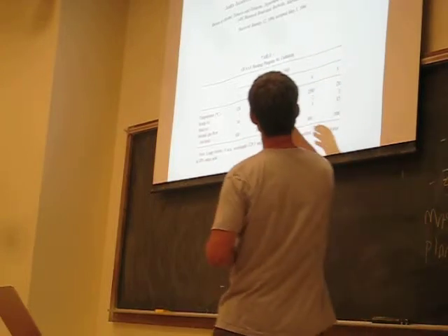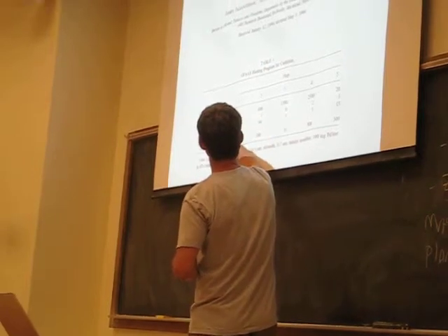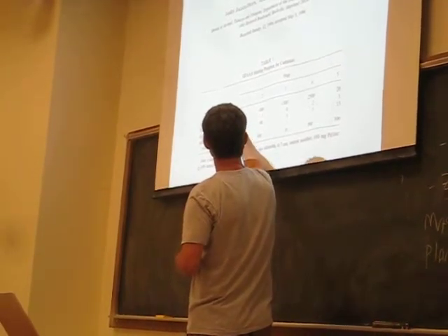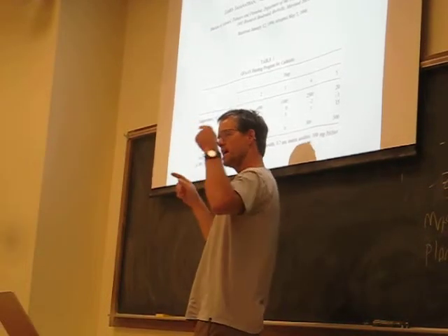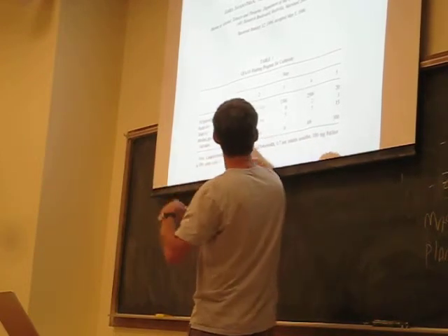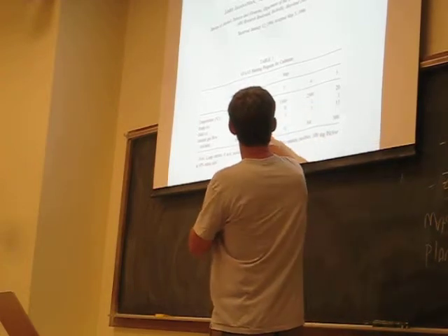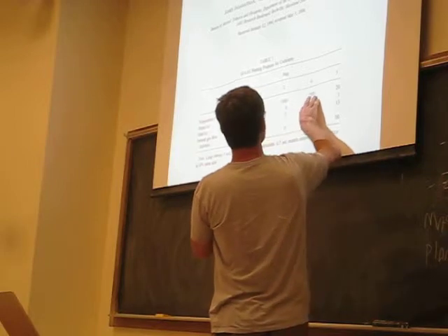And so they devised a graphite furnace atomic absorption program that we talked about, in terms of the temperature they're going to go to, how long it's going to take to get to that temperature, how long they're going to stay at that temperature, and what the flow of the inert gas is going through that tube to flush out the stuff that's evaporating off. This is what you would do if you did a graphite furnace method. You adopt and modify, if necessary, the program for processing your sample.